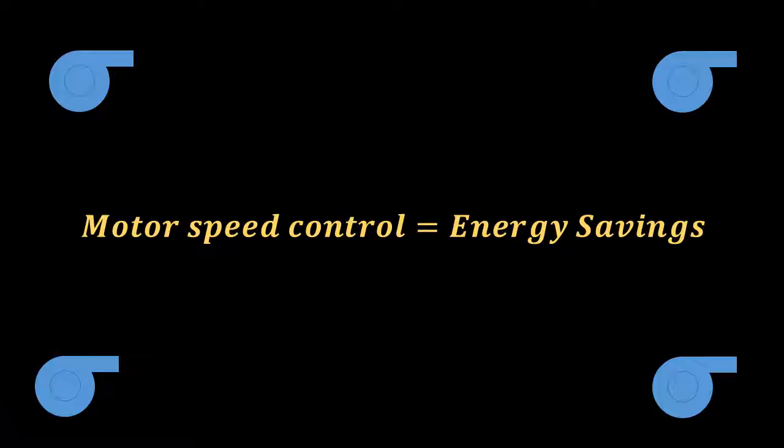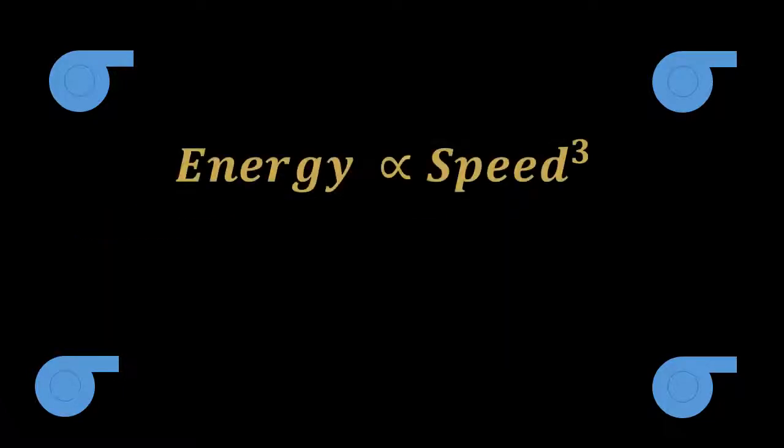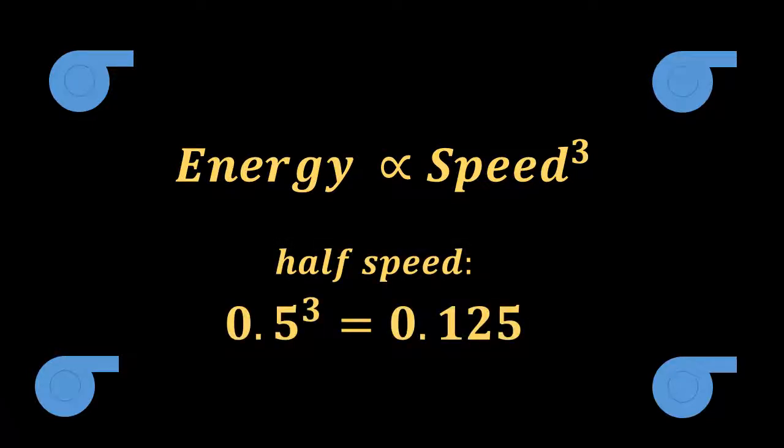For centrifugal pumps and fans, the input energy is proportional to the cube of its speed. Any reduction in speed will therefore have a much larger reduction in energy use. For example, a pump running at 50% of its speed only requires 12.5% of its rated power.